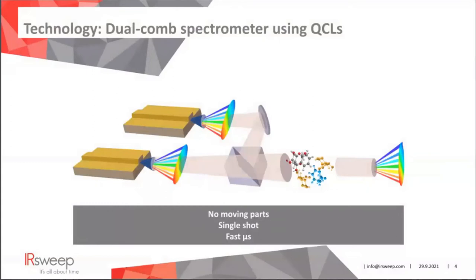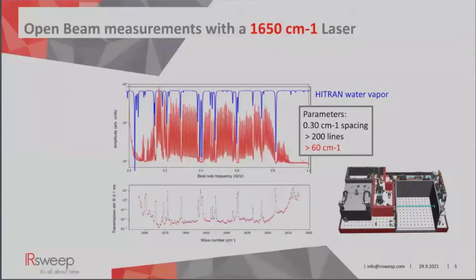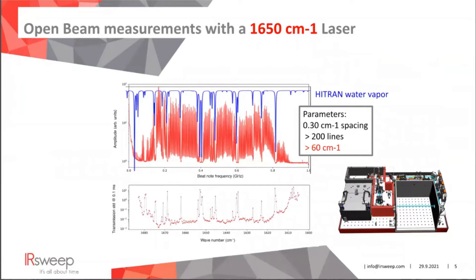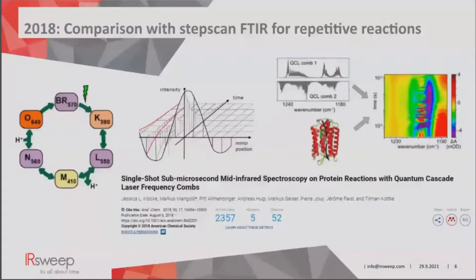Diving a bit more into the technology: two frequency-comb beams are mixed on a beam splitter and detected on a high-bandwidth MCT detector. Each pair of optical modes produces a radiofrequency beat note. The radiofrequency spectrum can then be measured with conventional electronics and represents the optical spectrum. With an open-beam measurement, we present a heterodyne signal obtained with a 1650 wavenumber laser, which is often used in protein dynamics, and a water vapor spectrum shows the information of the primary heterodyne signal in the same range.